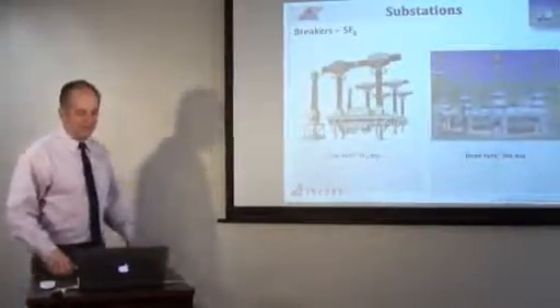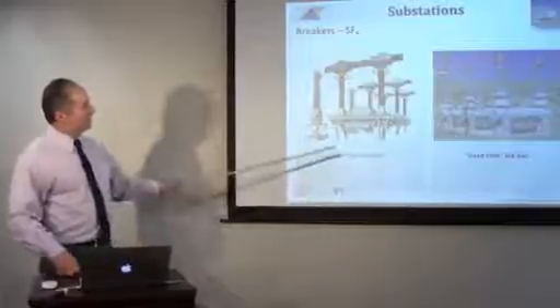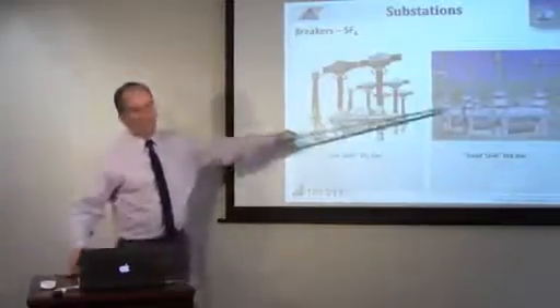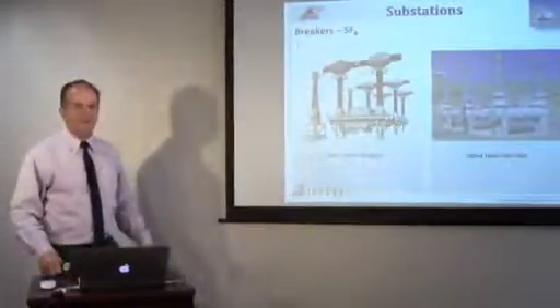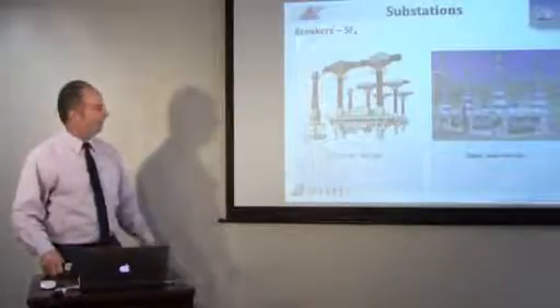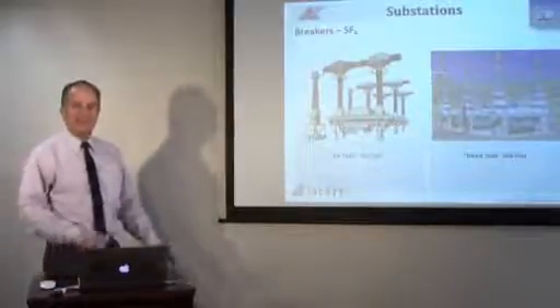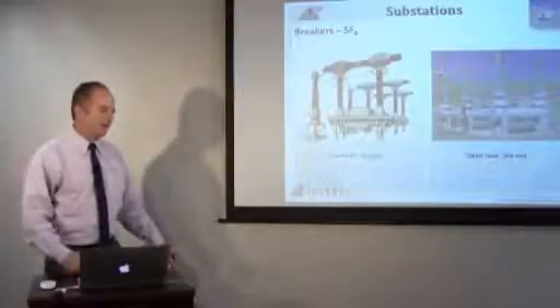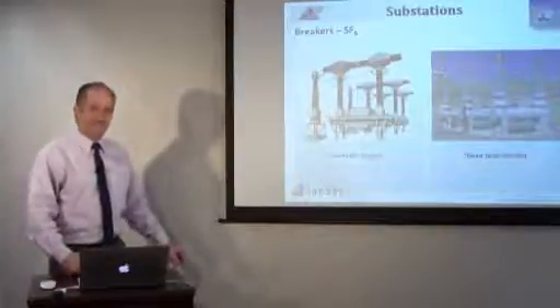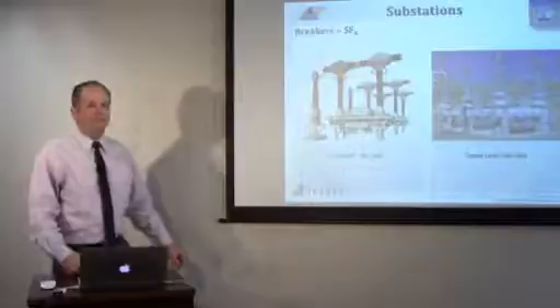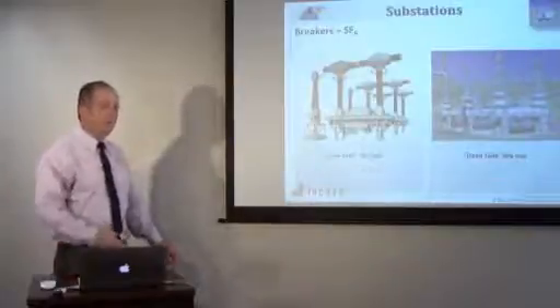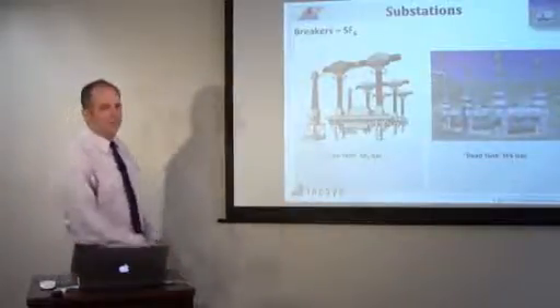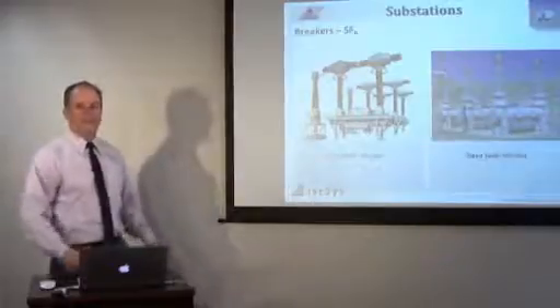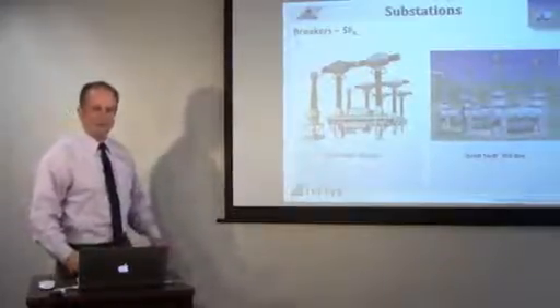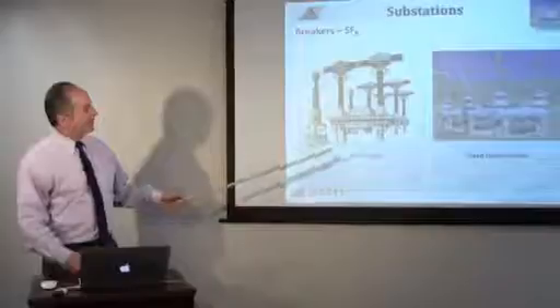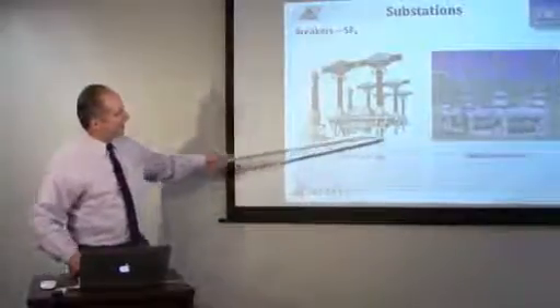Now, talking a little bit about circuit breakers, these 2 breakers here are SF6 gas breakers, sulfur hexafluoride. It's an inert gas, it's a safe gas, it's extremely high dielectric strength, much, much better than oil, but it doesn't have any cooling properties, so you can't use it in transformers really. I mean, there's some transformers out there, but they're getting cooling a different way. But this is a live tank versus a dead tank.